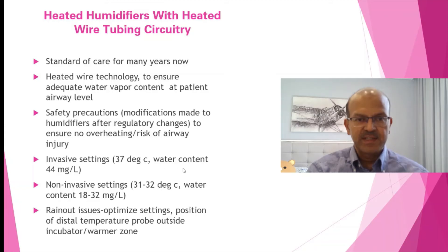At invasive settings, 37 degrees, the water vapor content is 44. And in non-invasive settings, the water content is 18 to 32 milligrams per liter. If there are rainout issues, you need to optimize the setting.